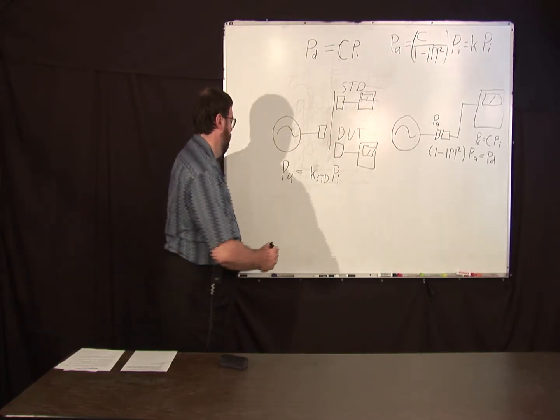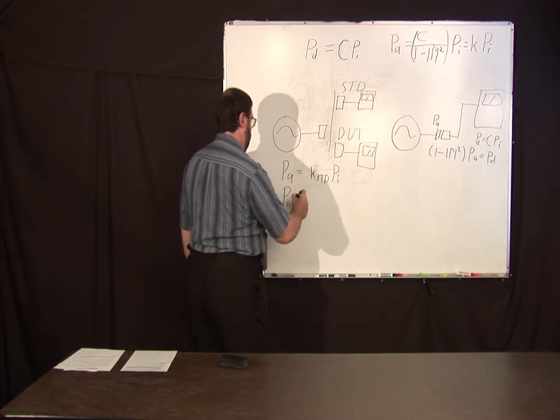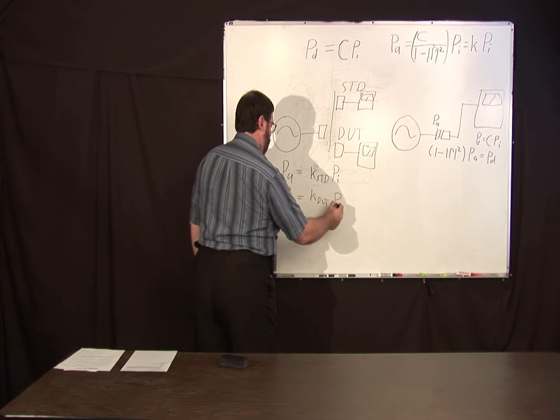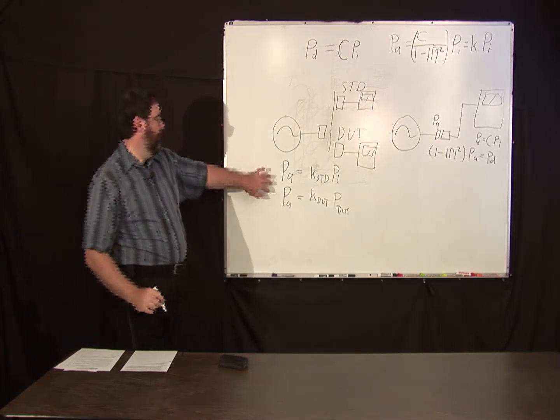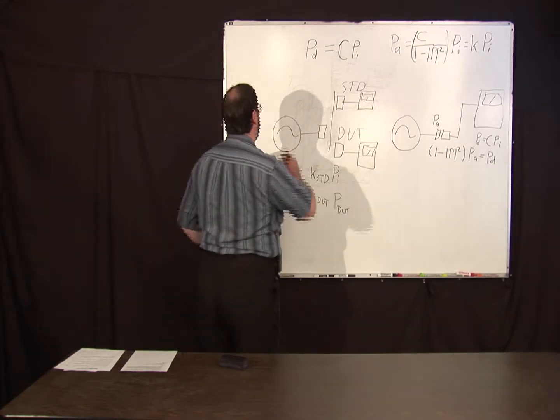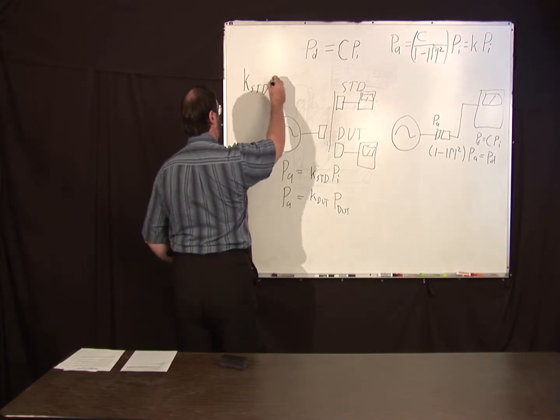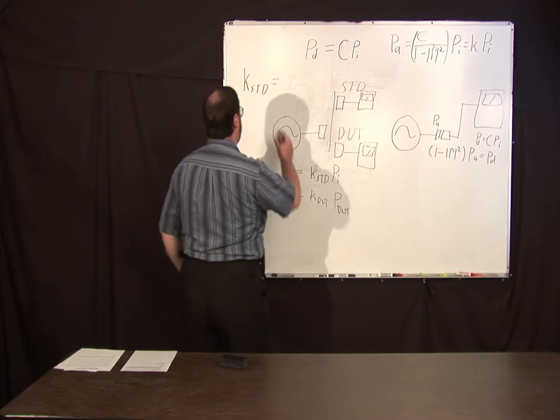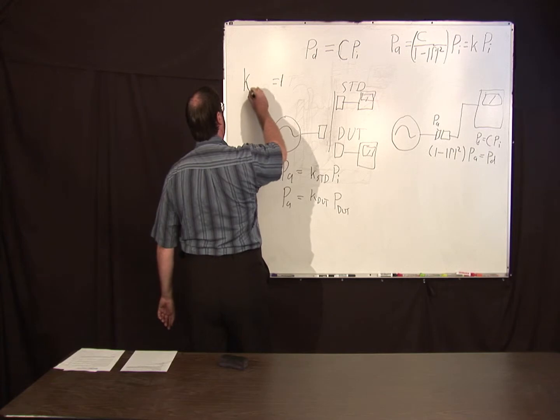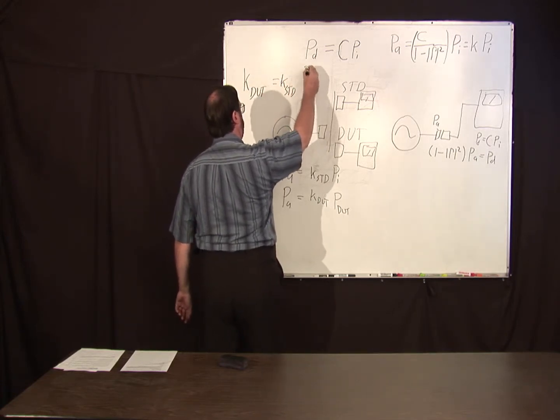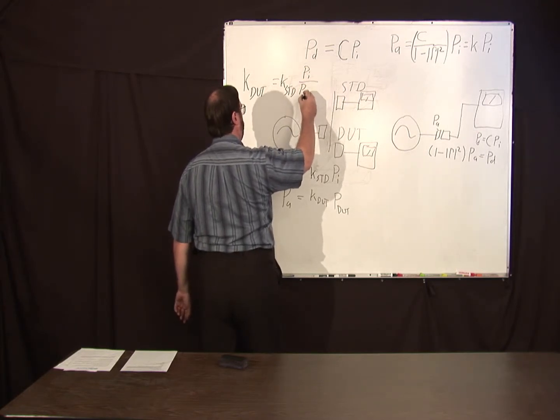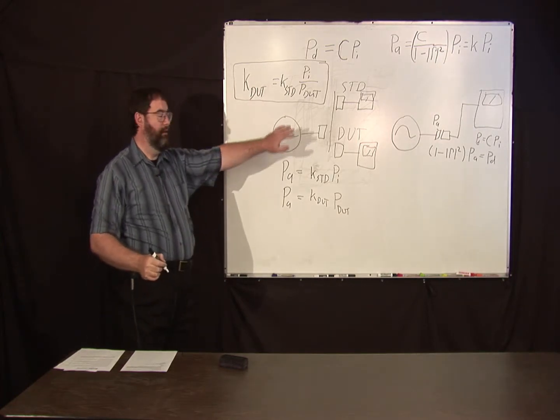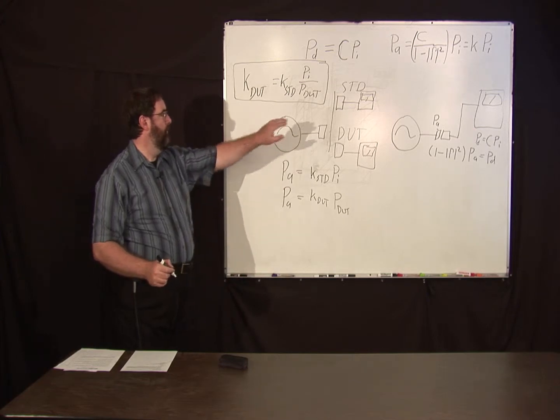Then we put the DUT on there, and we measure the available power, we measure some power. It's going to be K DUT, device under test, P DUT. So you can see, we can solve between these two, we can solve for this. K DUT is K standard times P I over P DUT. So that's one way of calibrating a power meter once you have something calibrated from calorimetry.